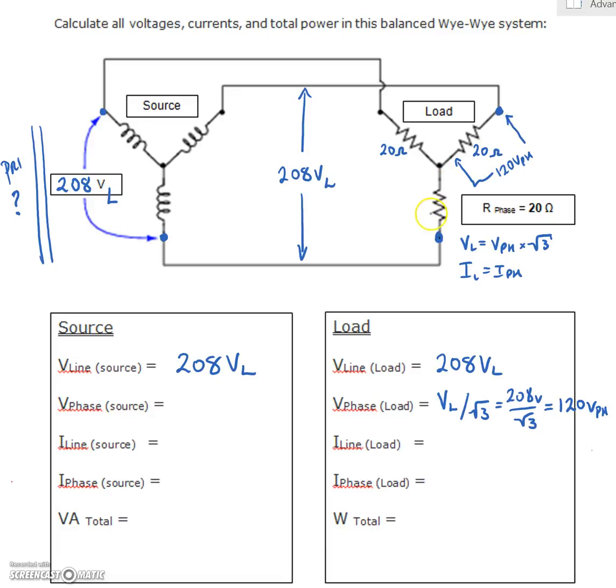So that voltage that we just found is our phase voltage. So that means that this voltage right across here is 120 volts on the phase. This voltage right here is 120 volts, and this voltage is 120 volts. From any line to neutral connection there, we have 120 volts. We don't need a neutral load because we have a balanced load. No need for a neutral to go back. Neutral only carries the unbalanced loads. These are mirror images of each other, so we know that this voltage here is 120 volts on the phase as well. And we can drop that guy in here across that winding.